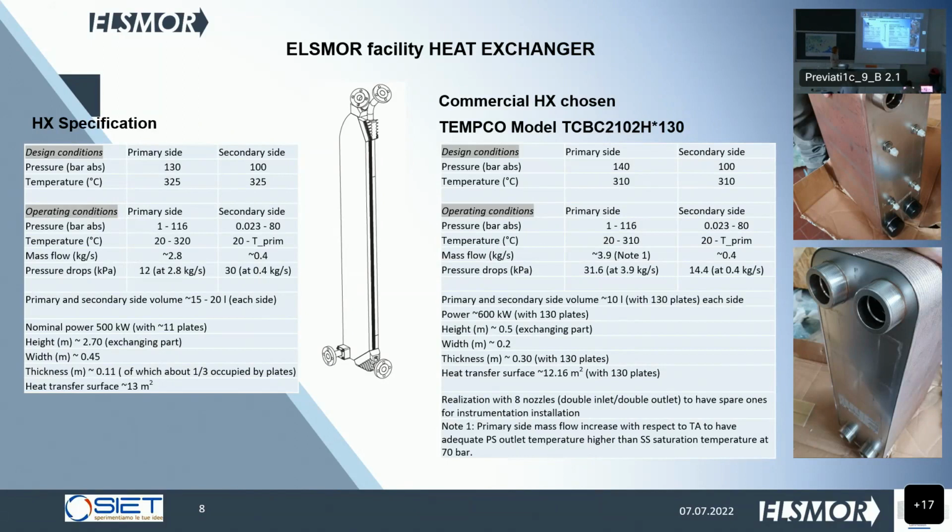And so in this table, we have the characteristics of this component, which is different in dimensions in terms of height, but from all the other points of view, pressure drops, heat transfer capability, it has adequate characteristics to be included in our testing loop.